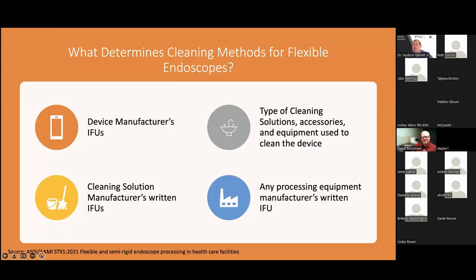As far as cleaning methods, those are determined not by the FDA, and people are always surprised by that. The FDA doesn't tell a manufacturer how to clean the device. It's up to the manufacturer to decide, validate, and prove that their method works.